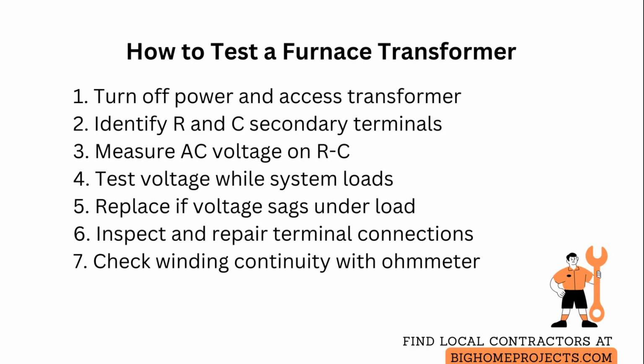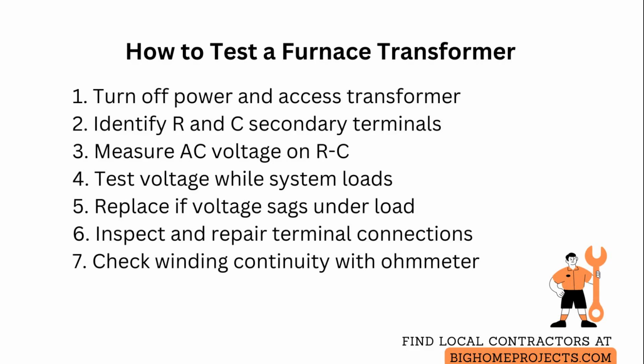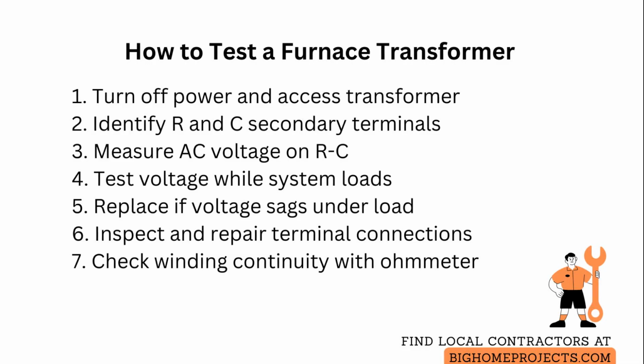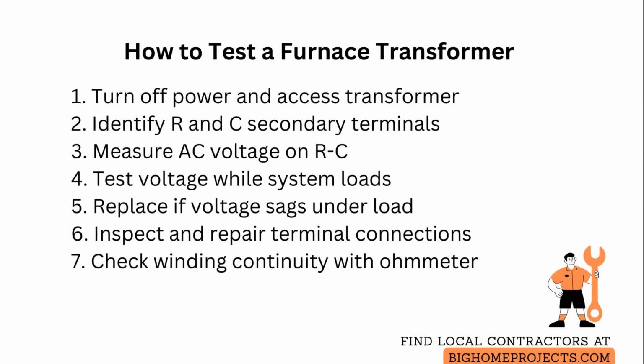If the voltage sags significantly when the load is applied, the transformer is overloaded or its internal impedance has increased and the component should be replaced with one matching the original voltage and equal or higher volt-ampere rating. Always confirm replacement units meet the furnace manufacturer's specifications to prevent control board damage.